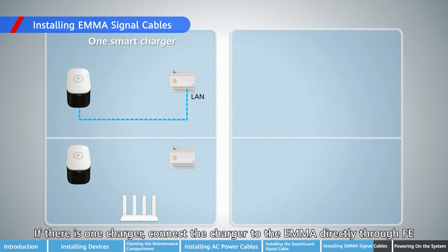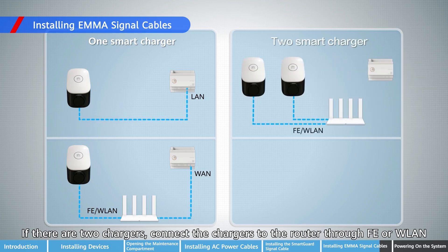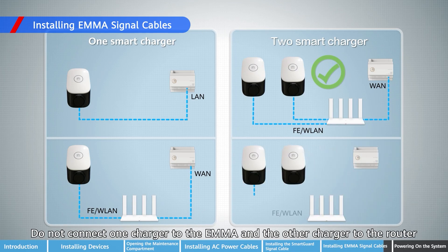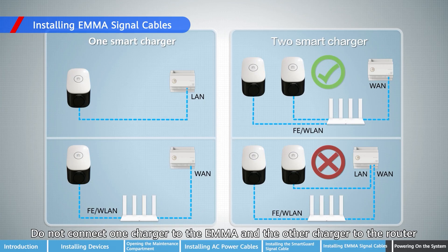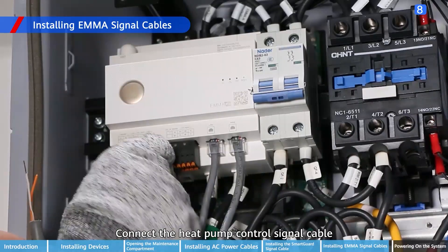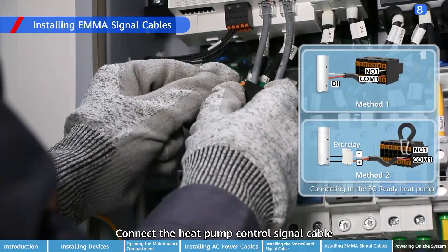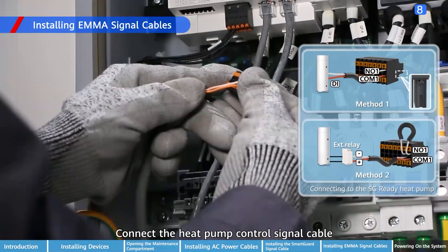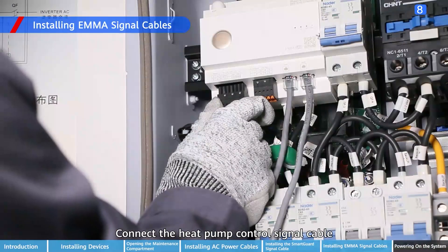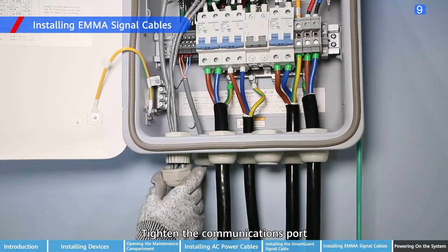If there is one charger, connect the charger to the EMMA directly through FE, or to the router through FE or WLAN. Do not connect one charger to the EMMA and the other charger to the router. Connect the heat pump control signal cable.